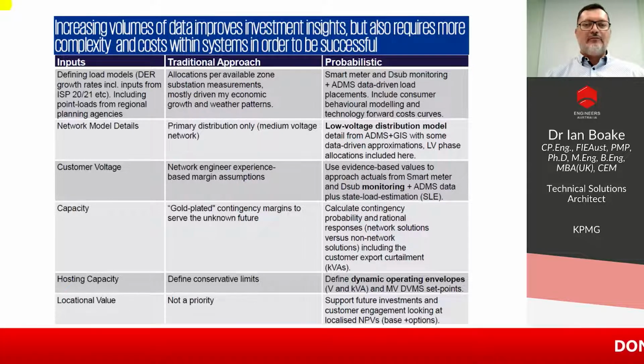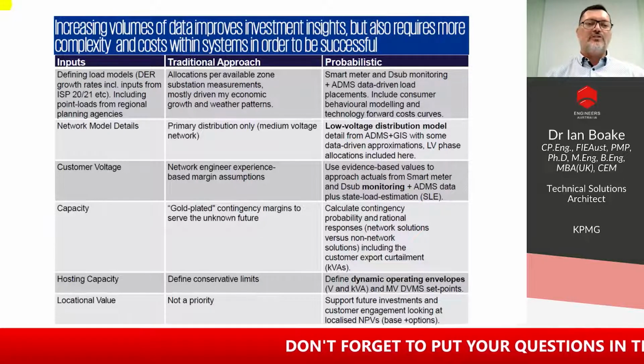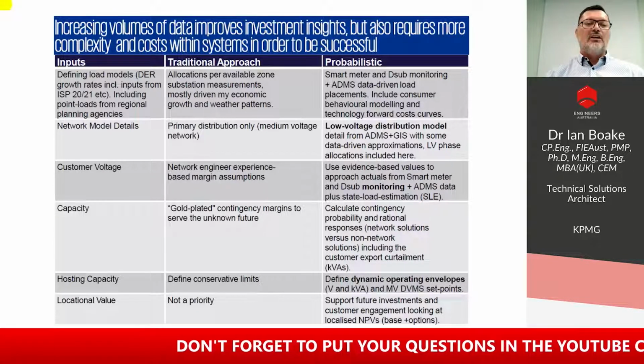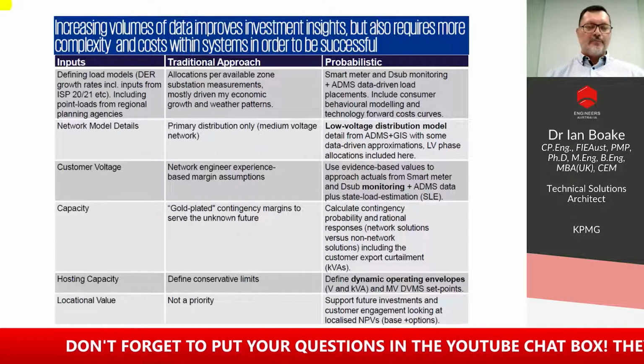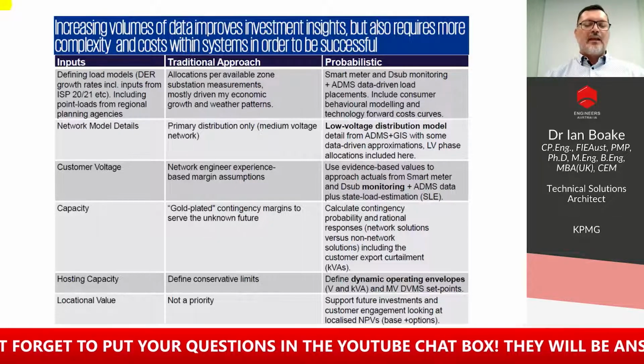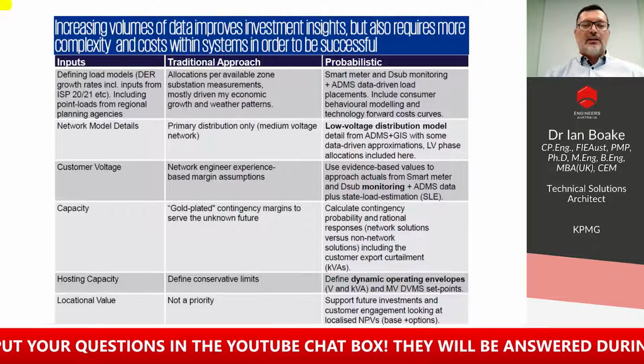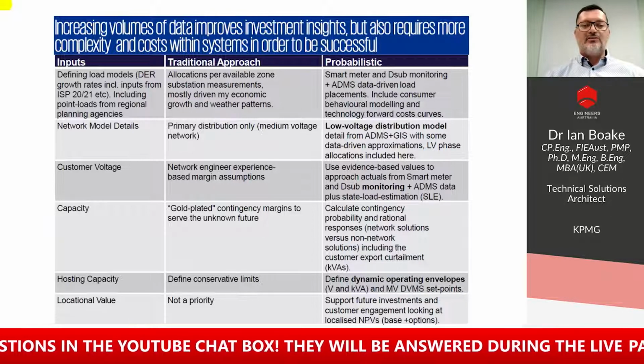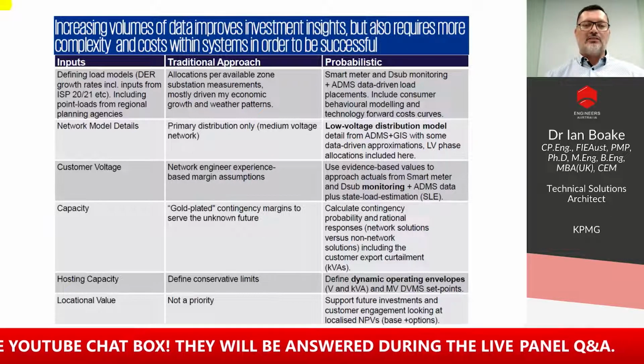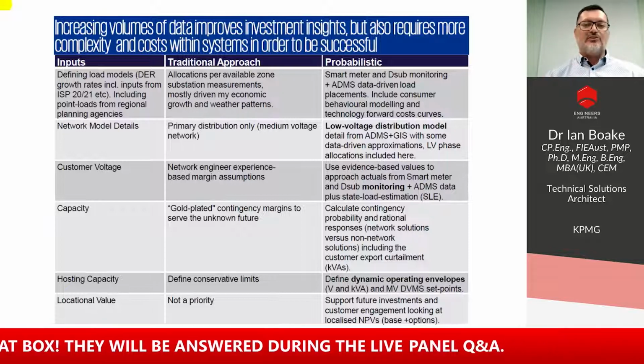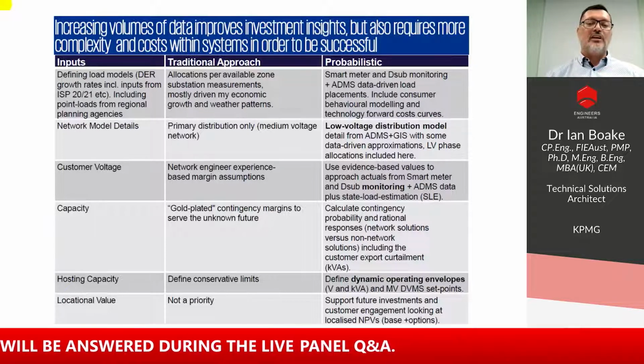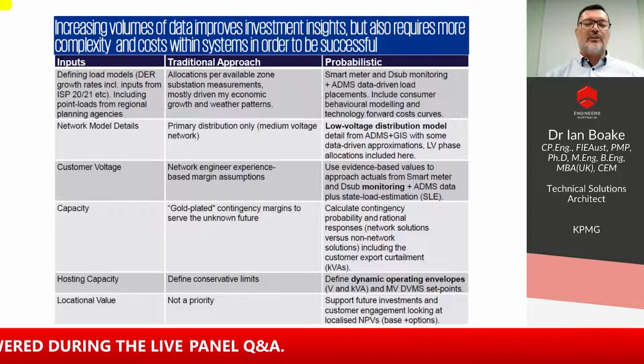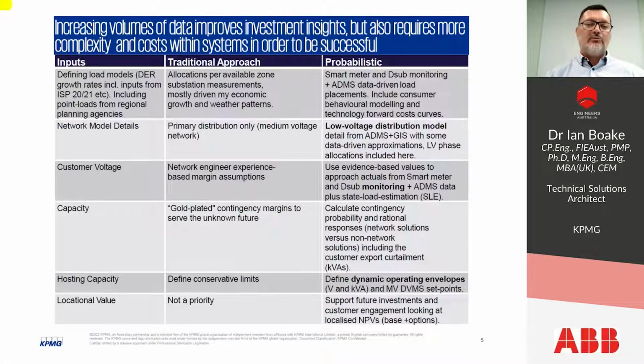So just to really emphasize the problem from the DNSP's perspective, there's a couple of issues that they have to consider. The first input is around the forecast. So how many DERs are going to come on at which stage in the future? And then they obviously have to provision zone capacity, zone transformers, which are the bulk supply points, then down to the distribution substations, and then right down to the LV network. So they've invested in what are called advanced distribution management systems to enable that.